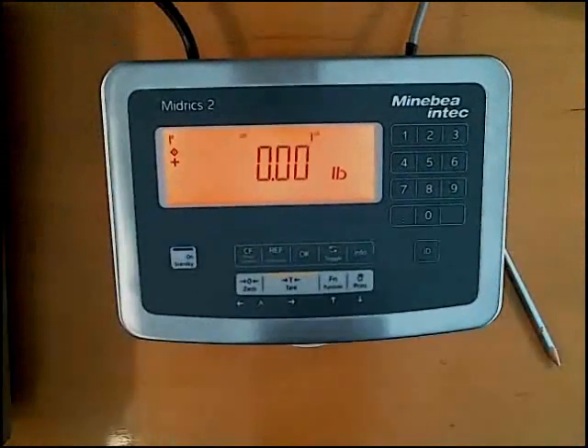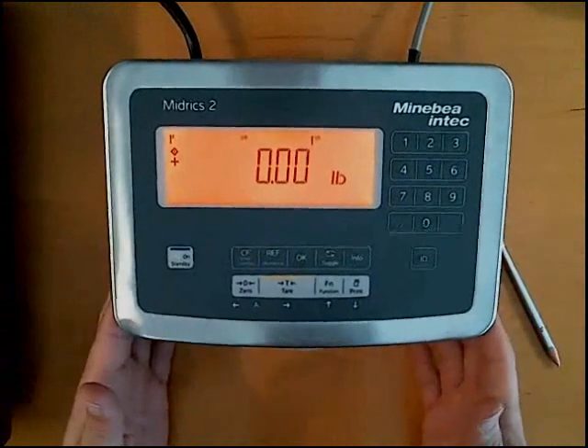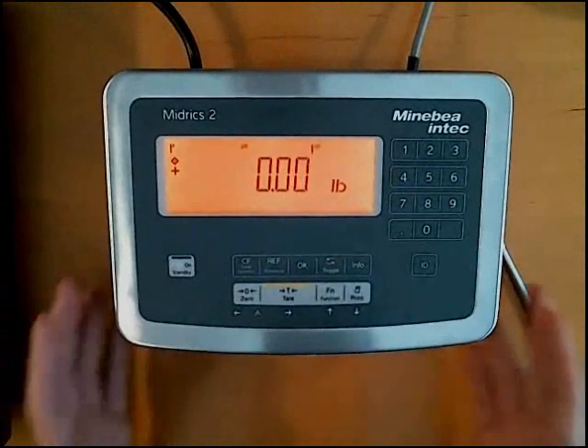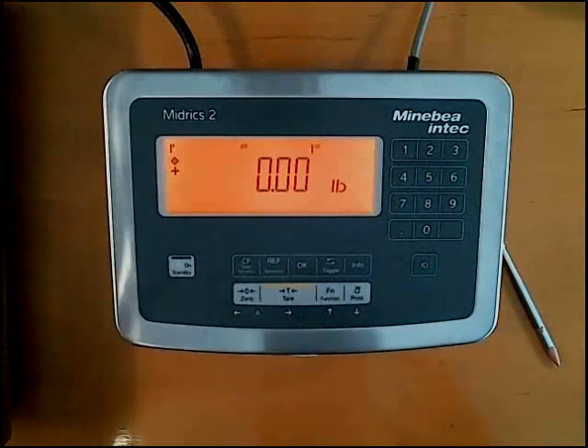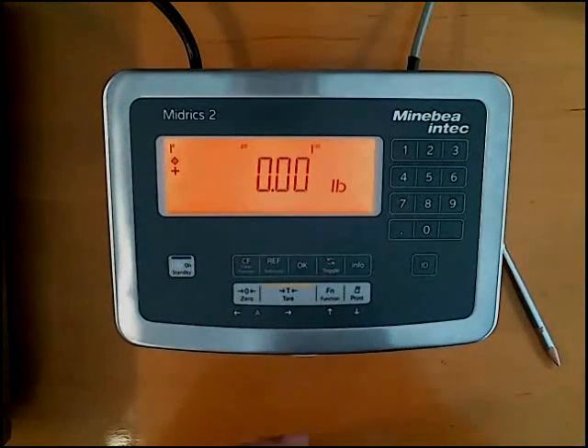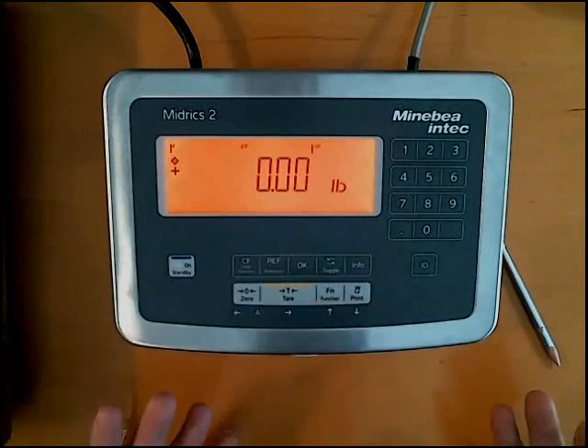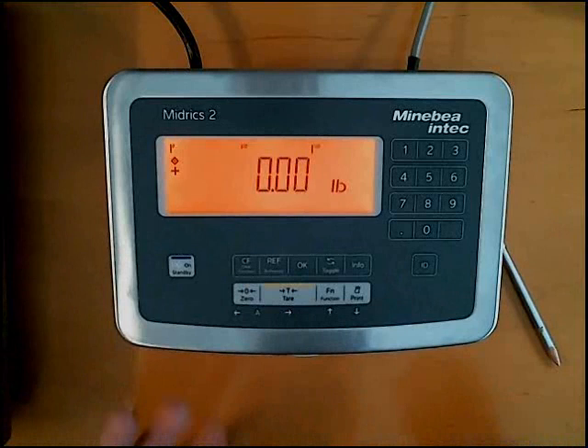It will also limit the calibration outside of an acceptable range. And what I mean by that is if I calibrated the scale at 5 pounds and then I go to do a calibration and I put 5 kg on by mistake, the scale will not allow me to make the adjustment. It says, I know what 5 pounds is. This is too far away, and so the calibration would not happen.